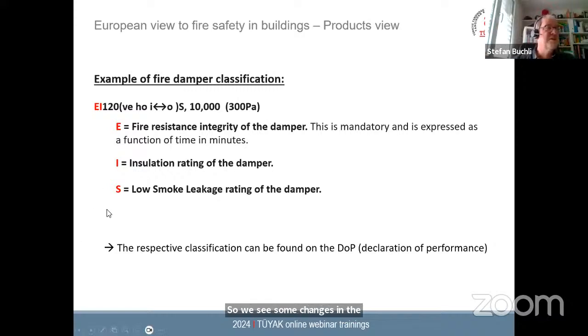And the S criterion is for low smoke leakage. So this is for really very low smoke applications, but this is also more or less becoming a standard. So a lot of the dampers, the bigger part of the dampers built into buildings, are EIS dampers today. If you look at the damper, go to the declaration of performance, you will find exactly the classification of this damper in this paper, and you exactly know what you get. This is why I really like the declaration of performance.